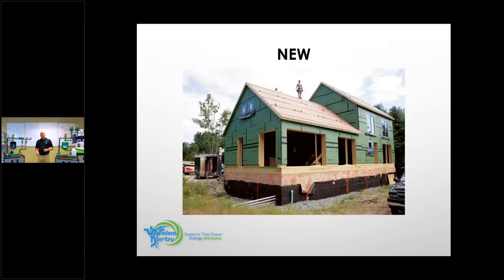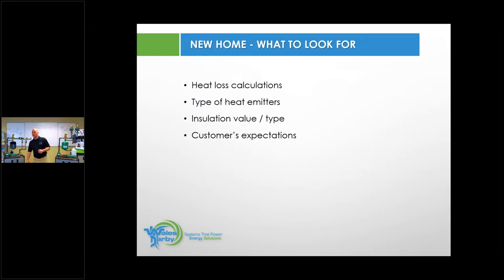So Bob the Builder called and says, I want you guys to come out. He had his architect and engineer give you a heat load calculation. So you got the heat load calculation and you're going to go there and say, okay, heat loss calculation. Yes, he has it, he's going to give it to you. If he doesn't have it, you're going to perform one. And then you're going to ask what type of heat emitters, because this is all going to help you figure out what type of appliance you're going to install in this job. Okay, so that's going to be important to you.